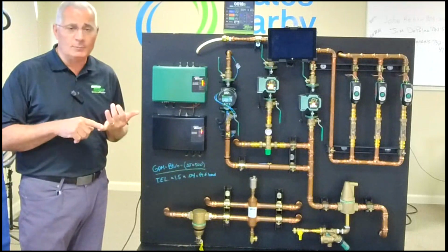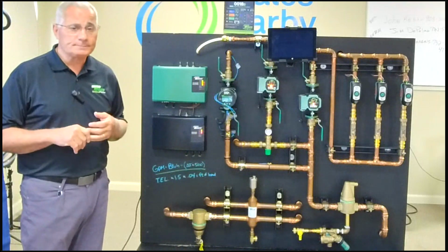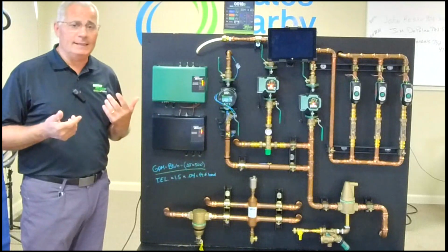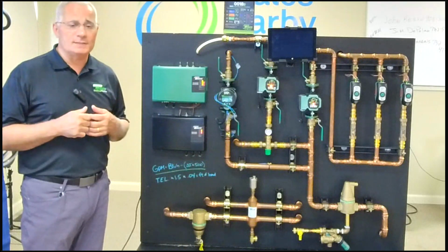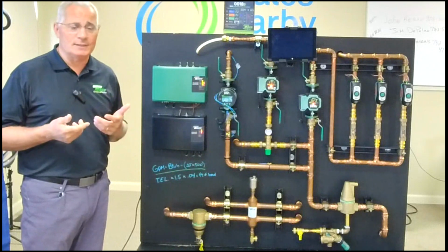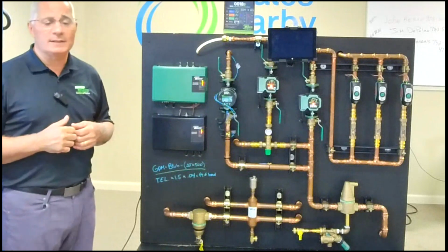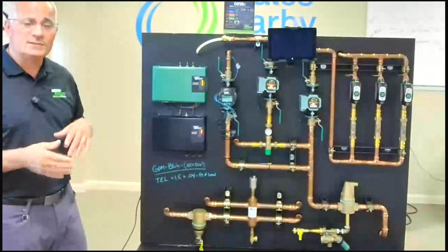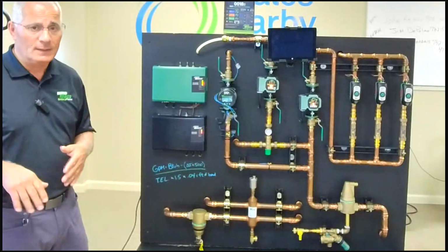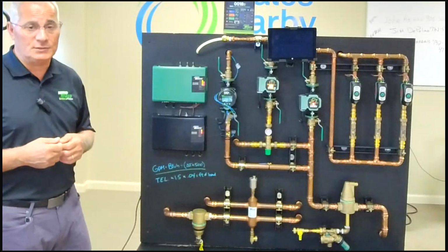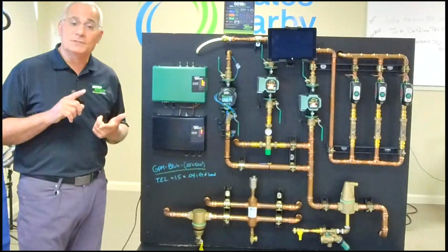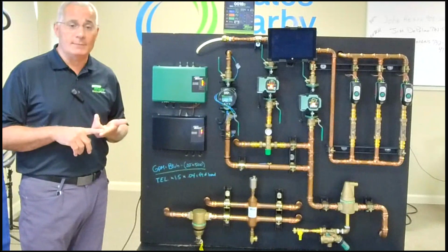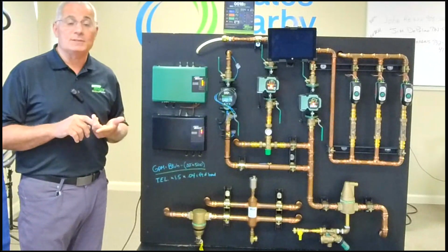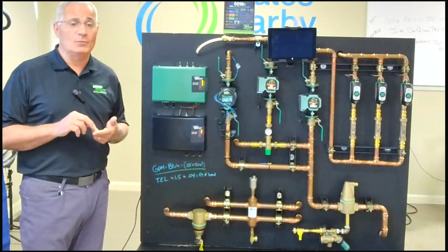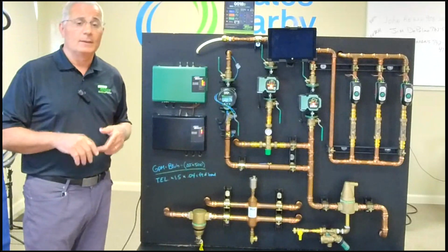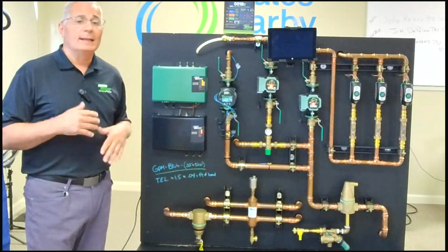That's either a Sentinel product or a Fernox product, and that's to clean the system. Any bad deposits, any corrosion that's in the system, we want to get it into solution. So when we come back a week or 10 days later, cut out the boiler, drain the system, all that crap comes out of the system. Because we don't want it getting into the heat exchanger of that condensing boiler, especially if it is a combi. Because the combi heat exchanger is even smaller, and I don't want crap in that system. So I pre-treated the system, cut it out. Now I've got to repipe.